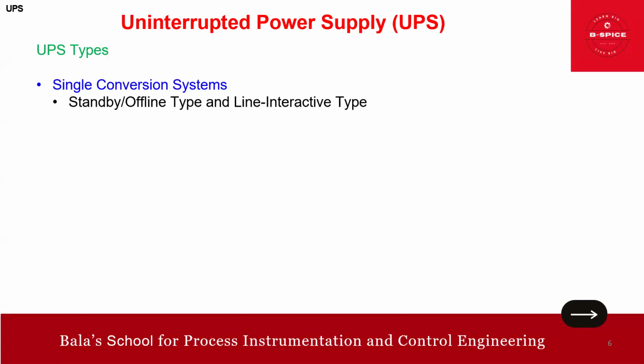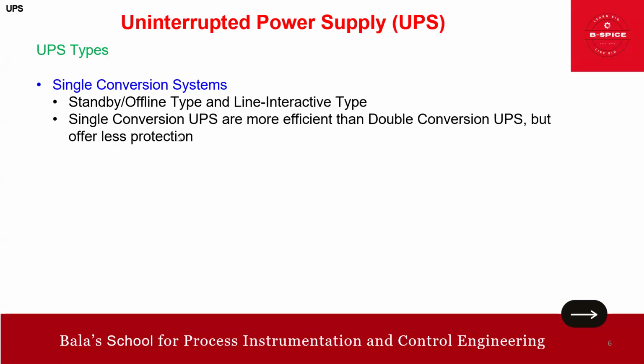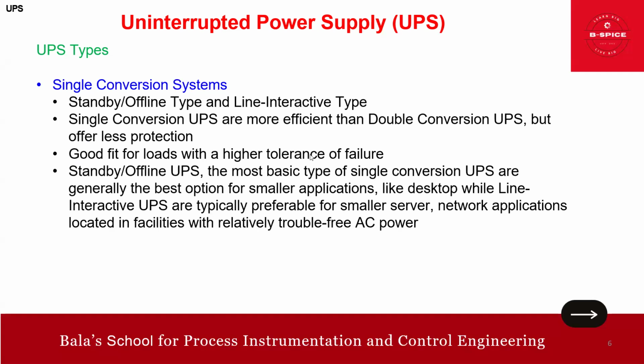In single conversion system, we have standby offline type and line interactive type. We'll talk about it with the help of a schematic. Single conversion UPS are more efficient than double conversion, but offer less protection. Considering the huge requirement in a big plant, protection is also important, so we will see that in double conversion. The point is single conversion is more efficient but offers less protection, and could fit loads with a higher tolerance of failure - meaning if we can tolerate, then we can use it.